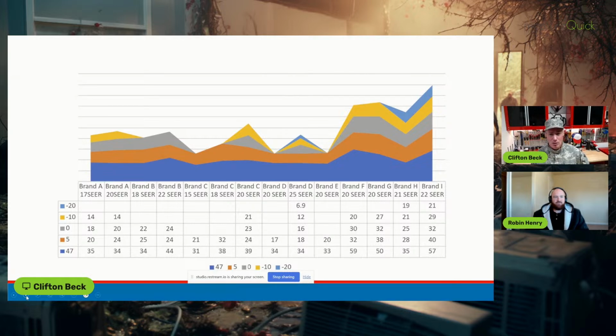You may look at a competitor's quote and say, let me check that for you - did you know the system you were quoted locks out at 5 degrees, and since they didn't include any supplemental heat, you have no heat below 5 degrees? And they say, well, they didn't tell me that. Yeah, don't gloss over that - you don't want to get that phone call. Those extended heating data tables are very important. Most manufacturers have them available, and there's also the NEEP database, but it's critical to do those load calculations.